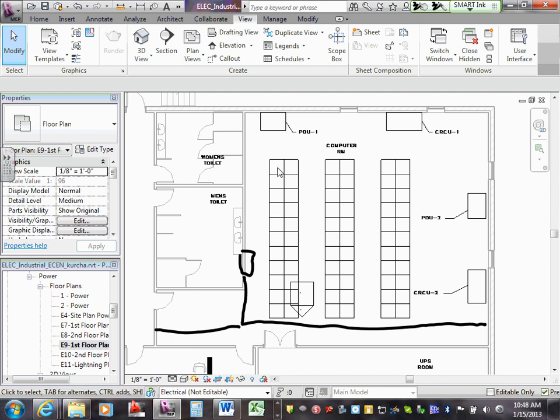What these squares, guys, these are racks full of computers. Each one of these squares, imagine a rack, say 7 feet high, full of computers, servers. Remember how Michelle Cooley came and you see the PDUs, power distribution units. Each one of these squares will be fed from one PDU and the other PDU, 2 feeders coming to them. So there's a lot of wires right underneath this first one, tons of wires. The smoke detector underneath there, if there's a fire, right underneath, we put all these wires on power system. We need to be able to recognize it and act on it. Am I right here, man? So that's kind of the whole idea.